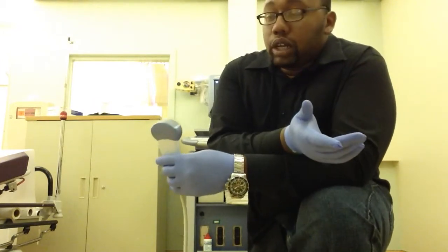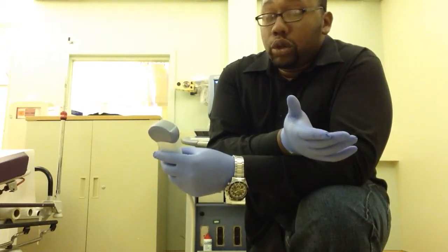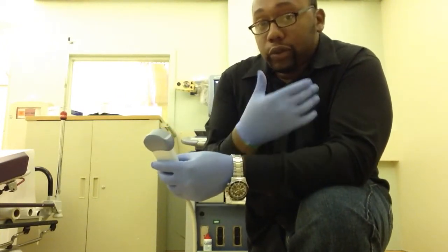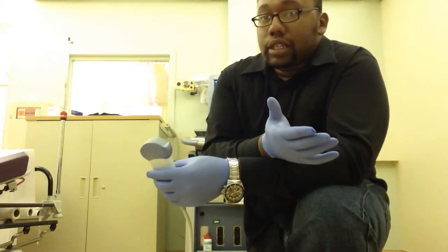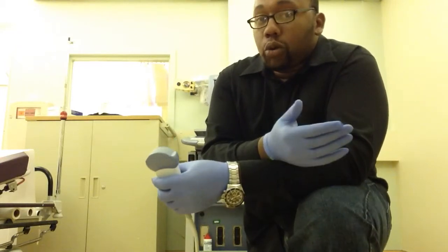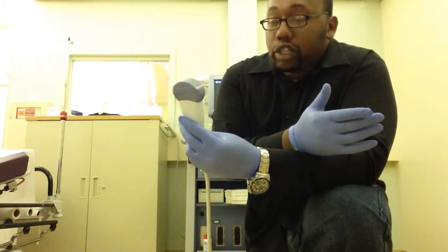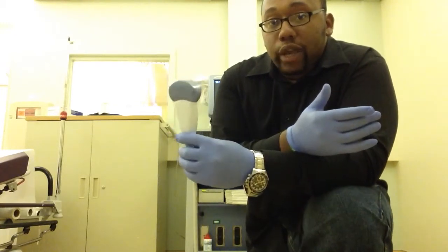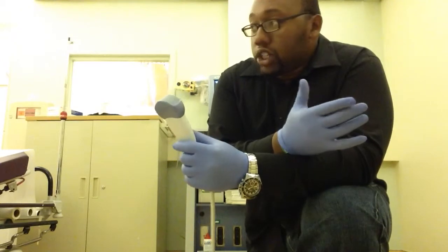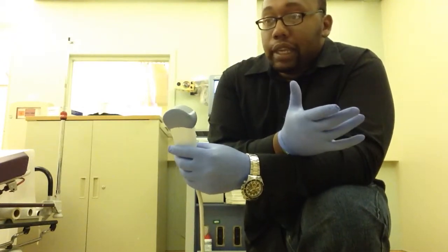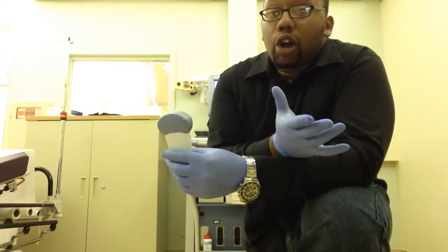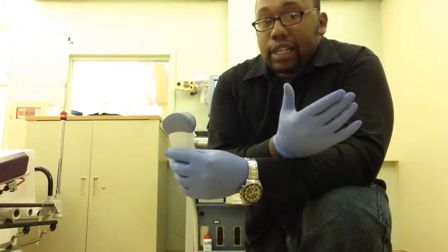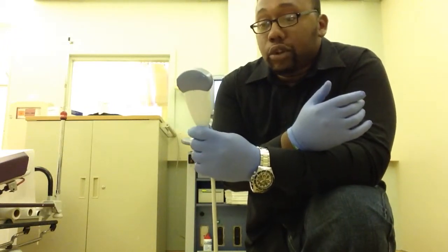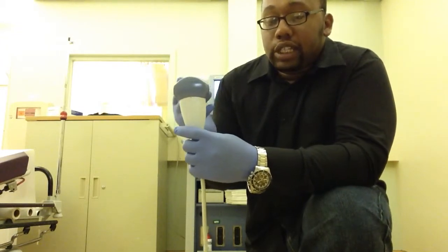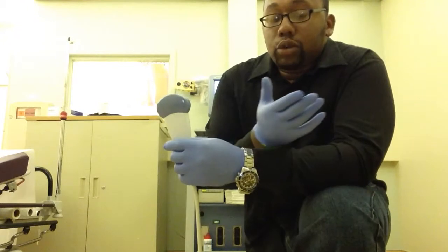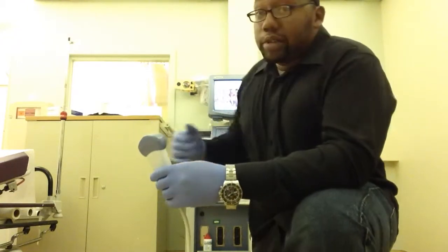The reason we do that is because sound travels through mediums such as water or the fluids in the human body, and when it hits solid objects, some of that sound is echoed. It's kind of how sonar works, and this is how we produce an image with these transducers. An ultrasound wave is emitted across the piezoelectric material and travels through the human body to a certain depth, maybe hitting bone, or, say, we're examining a gallbladder. Upon striking that gallbladder, some of that sound is echoed and returned to the transducer, so it also works as a receiver. The analog data received by the piezoelectric material is then converted into digital data and sent back to the computer, and that's how we get an image on screen.